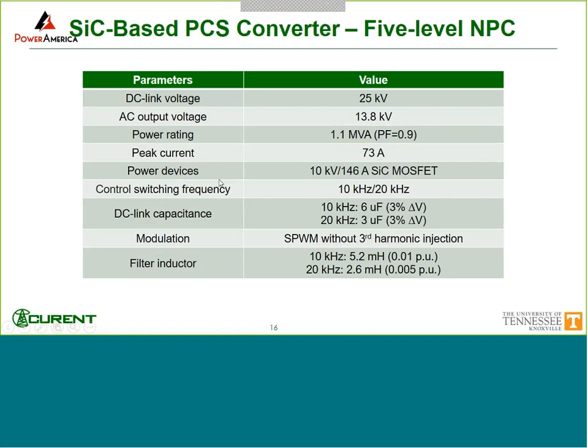Similarly, this is for the five level NPC using silicon carbide, 10 kV silicon carbide, and so these are the results. And we actually have done two different designs. One is a 10 kilohertz design, the other is a 20 kilohertz design. And again, this is a control switching frequency. So based on different frequency, we have some different passive requirements. The DC link voltage is 25 kV, and we choose to have no third harmonic injection because we don't have a transformer, so we have to take care of the common mode voltage.